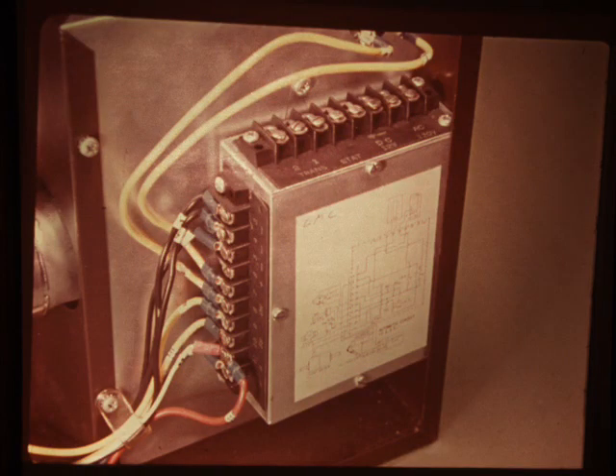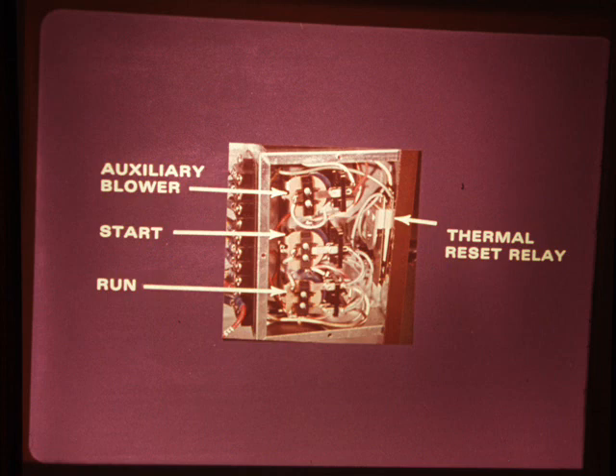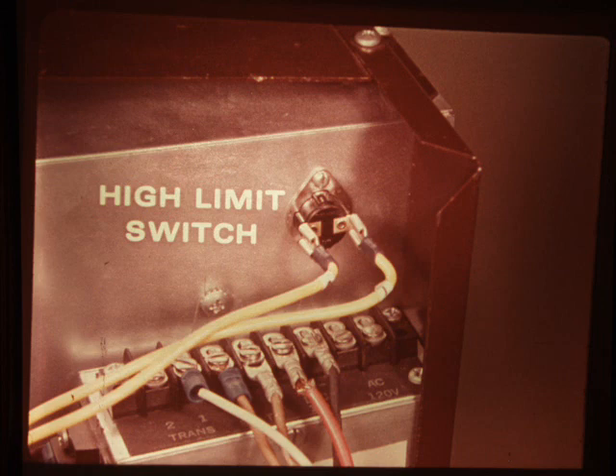The control box has thermostat and power connections at the top and connections to the other components at the side. They are clearly identified to correspond with the wiring schematic. Inside are four relays: the auxiliary blower relay, the start relay, the run relay, and the thermal reset relay. The thermal reset relay is one safety shutoff device. Another safety shutoff is a conventional high-limit switch.